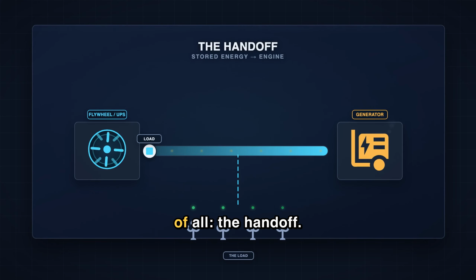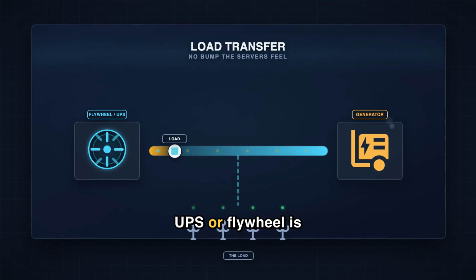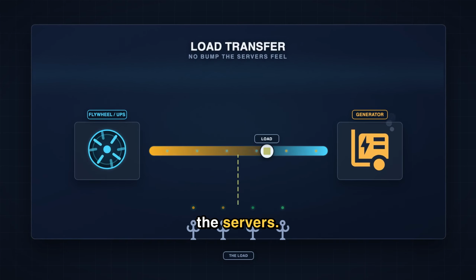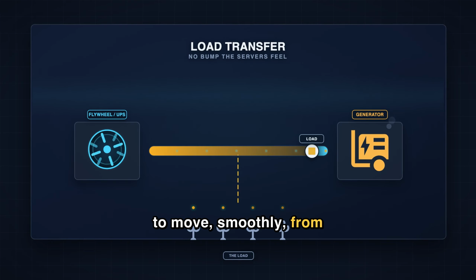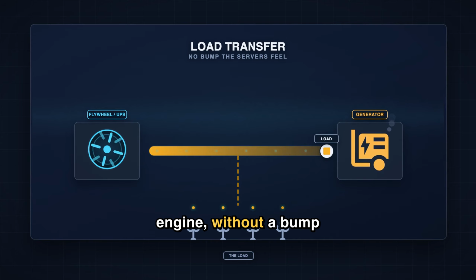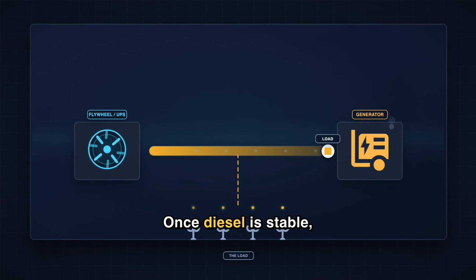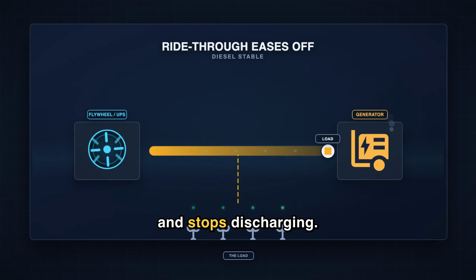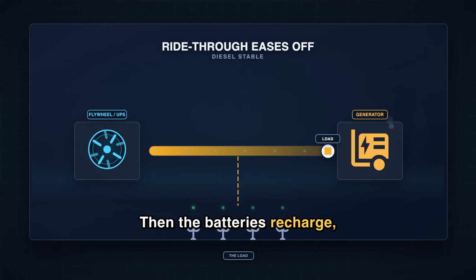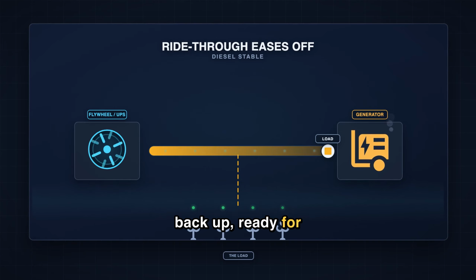Now the trickiest moment of all, the handoff. The generator is up and steady, but the UPS or flywheel is still the one carrying the servers. So the load has to move smoothly from stored energy to the engine, without a bump the servers can feel. Once diesel is stable, the ride-through eases off and stops discharging. Then the batteries recharge or the flywheel spins back up, ready for the next event.